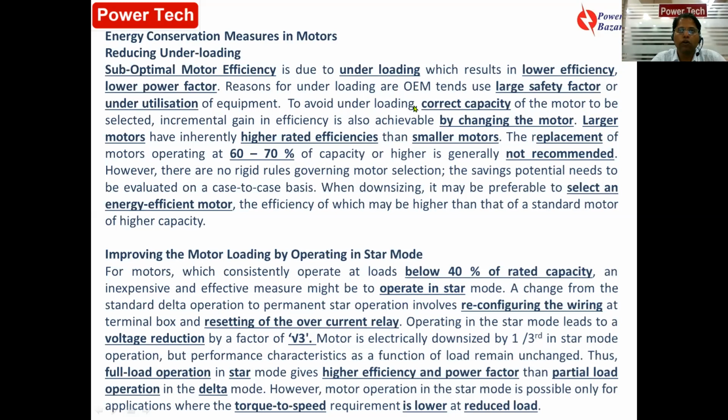After that, we analyze those data. We carry out how the motor is loaded, whether it is 50% loaded or 100% loaded or 75% loaded. And from those motor surveys, from those analyses, we find out what energy conservation measures are available in the motor. So today we'll discuss what the energy conservation measures in motors are.